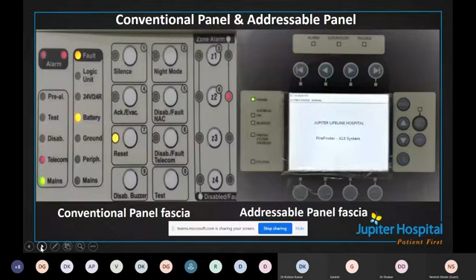Now, what is important is that when we say fire alarm system, the first thing is the smoke detector. There is always a question of where to put smoke detectors and where to put heat detectors. Normally smoke detectors are put in office areas or wherever equipment is there, and heat detectors are used in car parking, electrical panel room, kitchen, pantry. Then an LPG gas leak detector is used in the kitchen. Then a CO sensor is normally used in the fire pump area, parking, DG set room area.